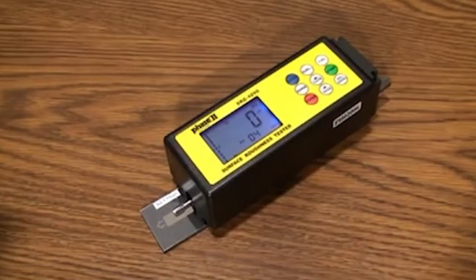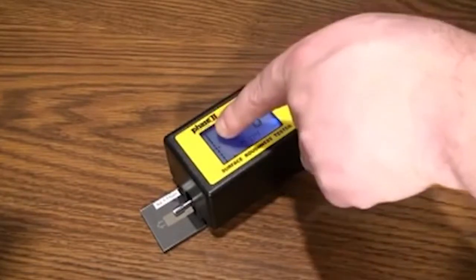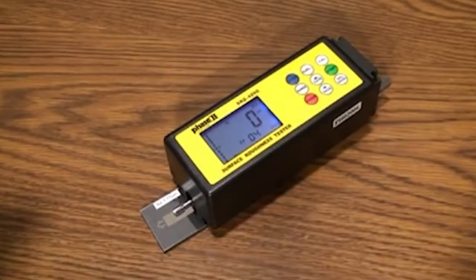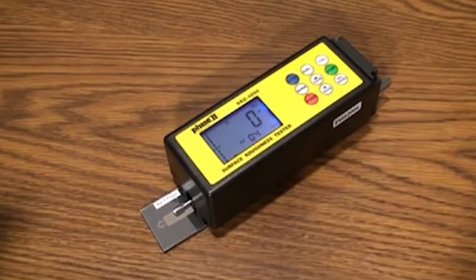Let's begin with leveling. You will notice on the left part of the screen a level with the zero centered. An arrow is showing to the left of the line. When stylus is in contact with the workpiece ready for test, this arrow should be in the zero range.